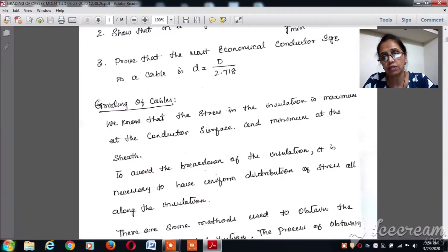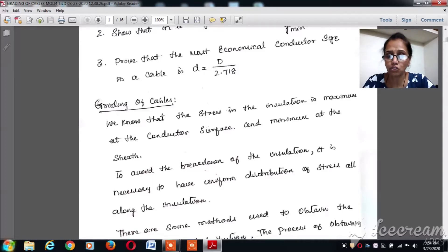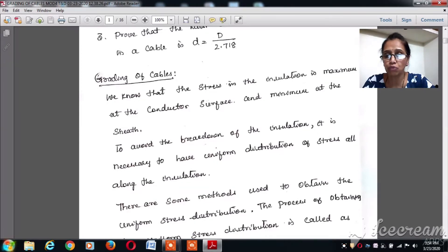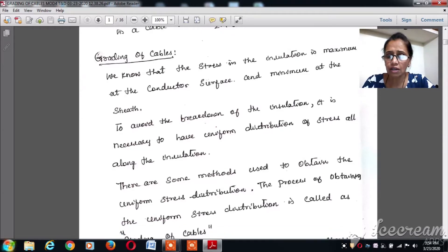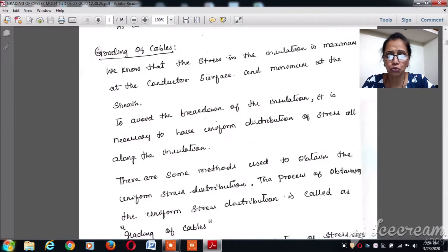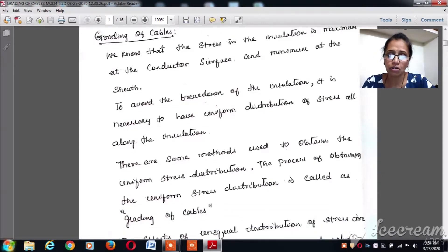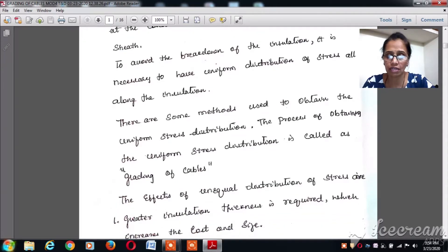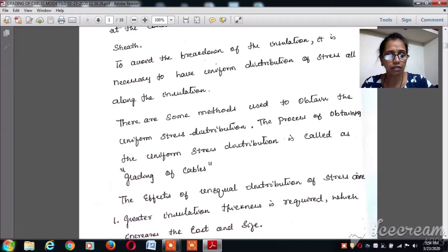The stress in the insulation is maximum at the conductor surface and minimum at the sheath. To avoid the breakdown of insulation, it is always necessary to have uniform distribution of stress all along the insulation. The process of obtaining uniform stress distribution all over the insulation of the cable is called grading of the cables.